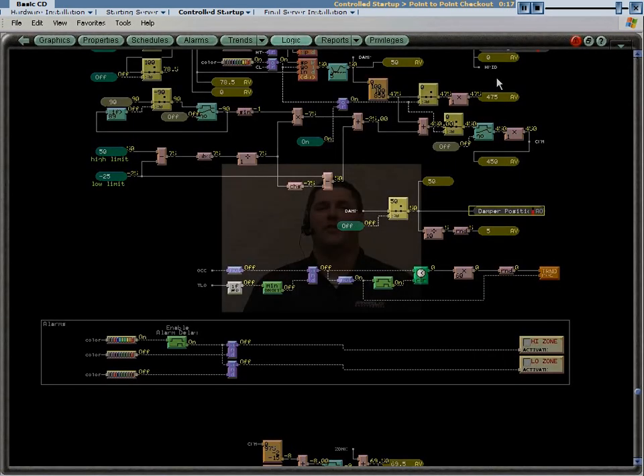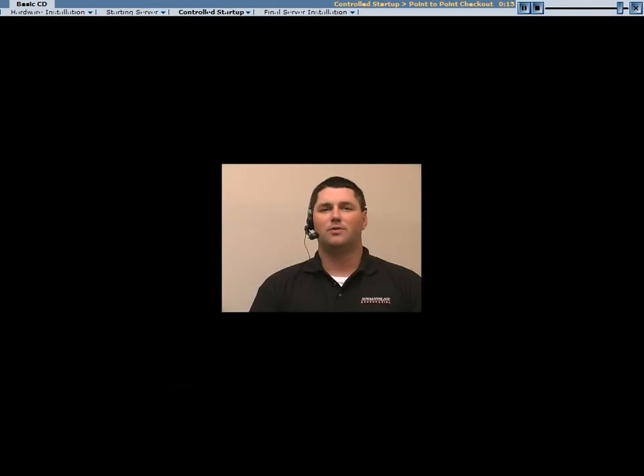In the startup phase, we will continue to use WebCTRL's logic pages and microblock pop-ups to make adjustments to tuning properties, set points, and other microblock values. The results will be verified using the logic page's dynamic status information.